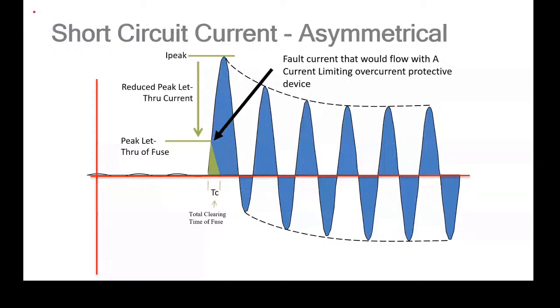So what happens is that transition of current, because of that slope, translates into magnetic forces in the circuit. The duration of the fault current that flows translates into heat. So what your goal is from a current limitation perspective is to not let 1, 2, 3, 4, 5, 6 cycles. That's 6 cycles of clearing time. You don't want 6 whole cycles, because that is a lot of heat, and that first half cycle is the magnetic forces that'll rip things apart. You want to limit the heat, so you want to get it to less than a half of a cycle, and that's about a quarter cycle.